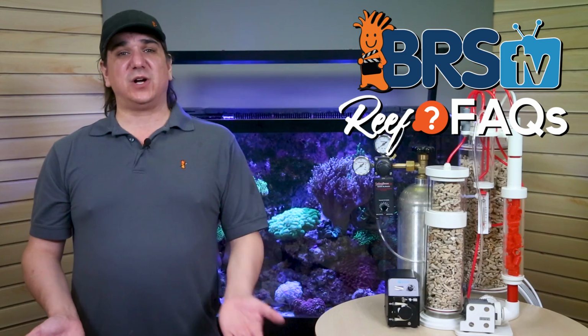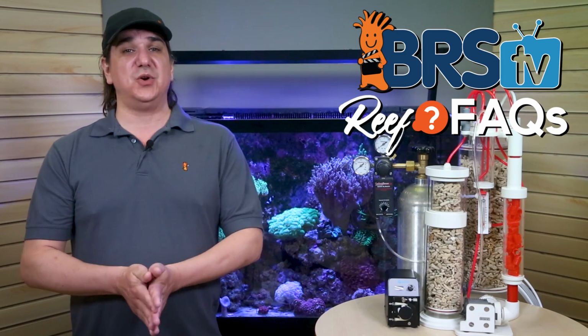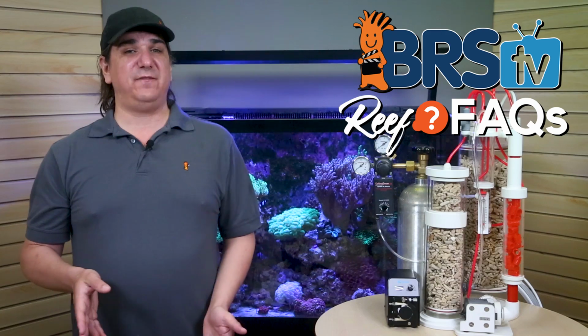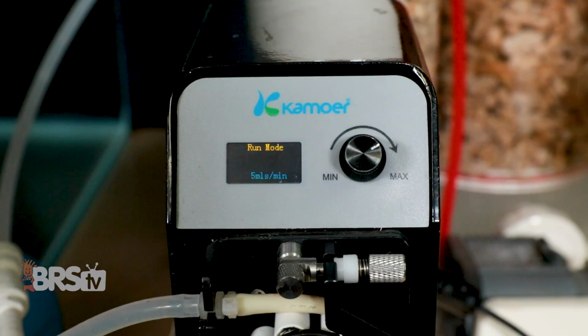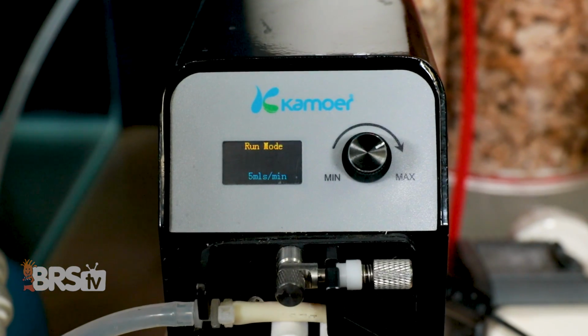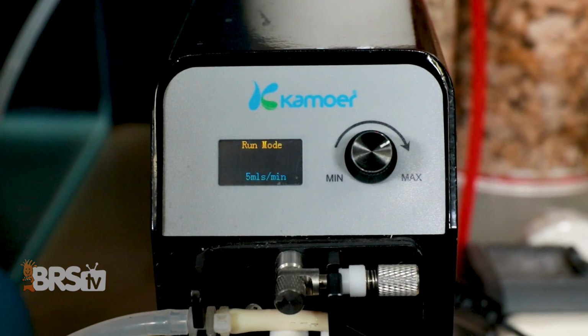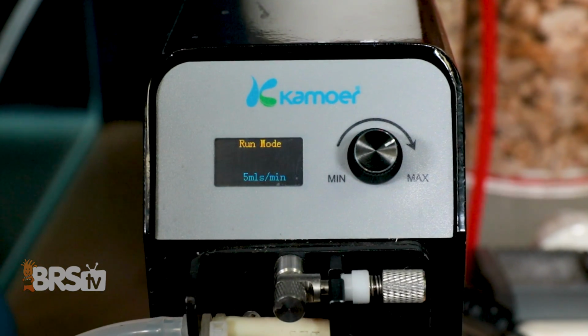The reason we recommend a more concentrated solution is because you can dose nearly half as much. The biggest benefit to dosing half as much solution is it'll make the dosing pump tubing last twice as long, the pump motor roughly twice as long, and when it spins slower, it's also a lot quieter.